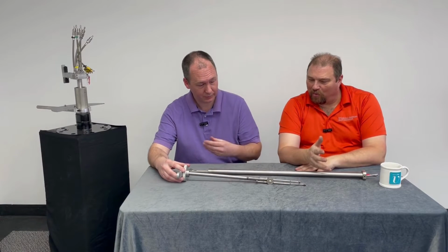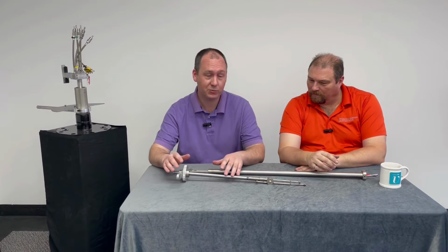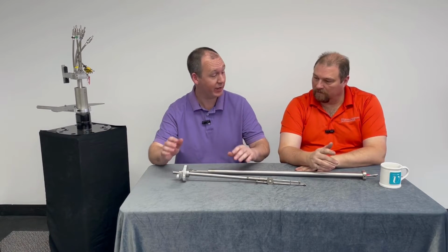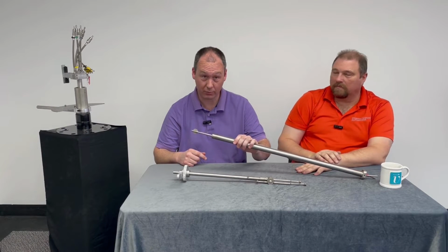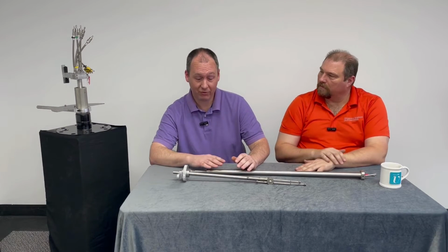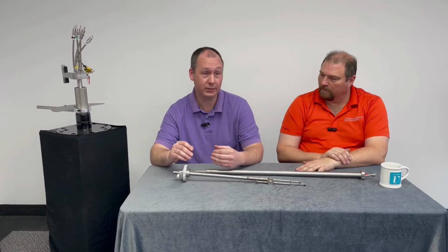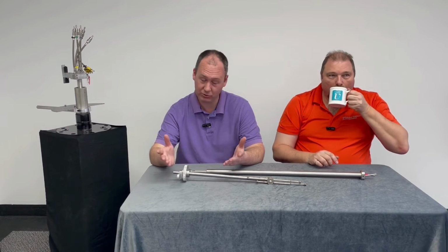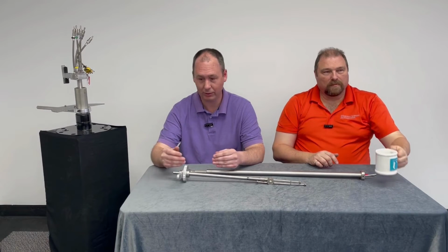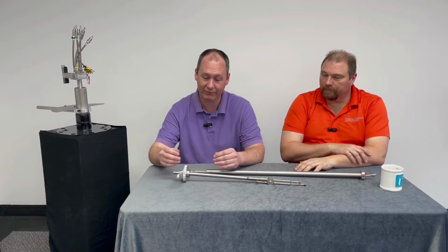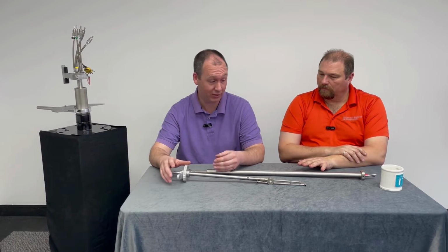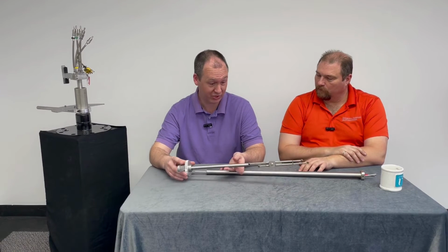So how does a probe like this work? So the way you use this probe is the first thing you need to do is measure the velocity and temperature in the pipe. So you actually use a different probe for that. You use the dirty air probe. Once you have that information, then you can take that velocity and temperature, put it into your spreadsheet, use your chart, put it into your electronic equipment, whatever you have to do the test. And then based on that, you set the vacuum rate for your sampling.